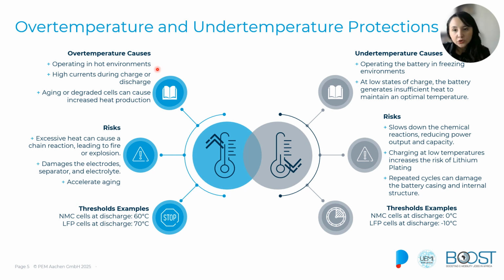As well, degraded cells usually have more heat production because their internal resistance is higher than in new cells. Another cause of over temperature protection is the chemical reactions within the battery that produce heat as one of the byproducts when the battery is being cycled. Another cause might be inadequate cooling systems or failures in the dissipation and thermal management system that can cause overheating. When we have cells that exceed the safe threshold, there is a severe risk. One is thermal runaway, or permanent damage in the cells, but also high temperatures are directly related to the accelerated aging of our batteries, which significantly shortens the battery lifetime.